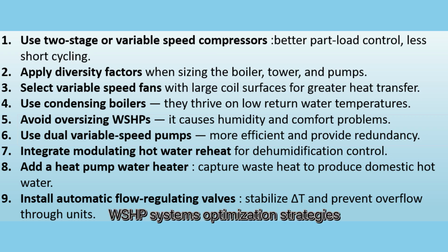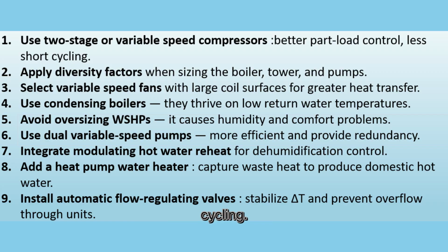WSHP systems optimization strategies. Use two-stage or variable speed compressors. Better part load control, less short cycling. Apply diversity factors when sizing the boiler, tower, and pumps. Select variable speed fans with large coil surfaces for greater heat transfer. Use condensing boilers. They thrive on low return water temperatures. Avoid oversizing WSHPs. It causes humidity and comfort problems. Use dual variable speed pumps. More efficient and provide redundancy.